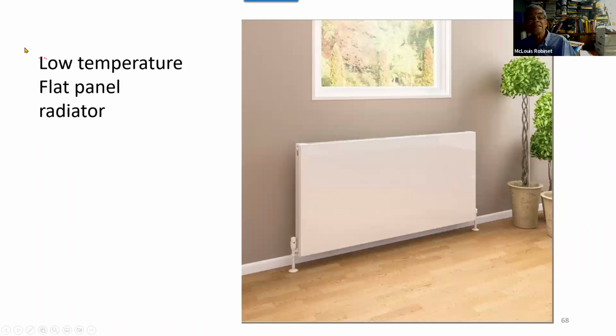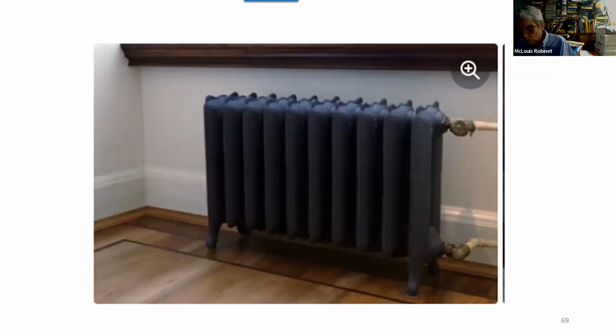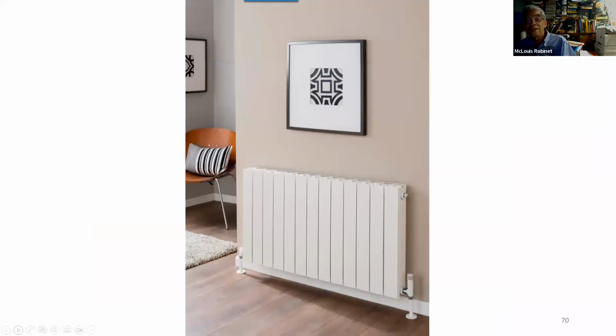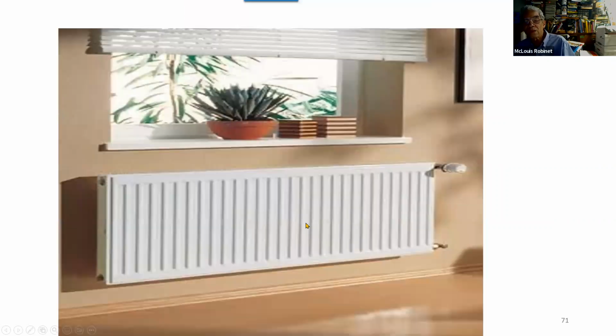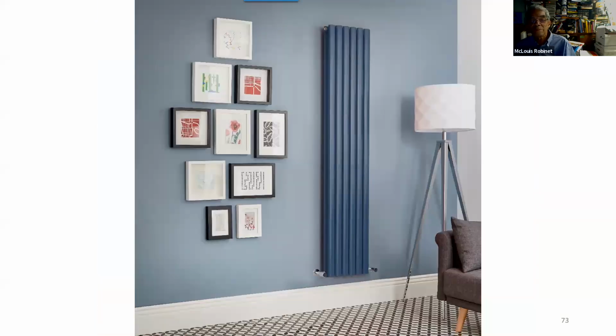So for example, this low temperature flat panel radiator has a surface area of 3 or 4 times greater than this one. So if one wanted to switch from a conventional hydronic system, where you have a high temperature boiler with conventional radiators, one option would be to switch to an air to water heat pump and use plate radiators. So it can be pretty fancy, but that's in a heating mode.